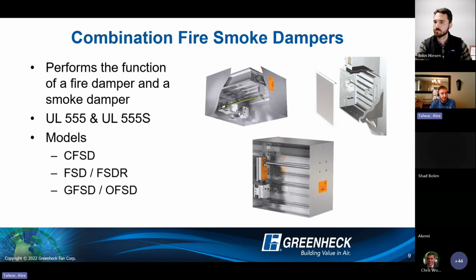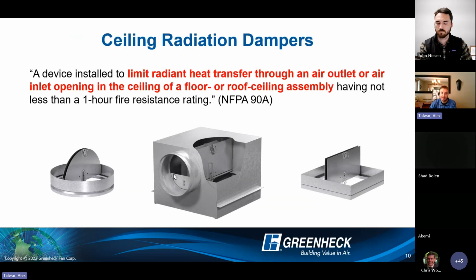Obviously, as the name suggests, the combination FSD products perform the function of both an individual fire and smoke damper, so they carry both the UL 555 and 555S rating. FSD is the typical fire smoke damper. The CFSD is the corridor fire smoke damper product that gets installed horizontally in the tunnel corridor construction. And then at the bottom there, you see GFSD and OFSD. Those are special out-of-wall models. We'll talk a little bit more about those later once we get into the installation phase.